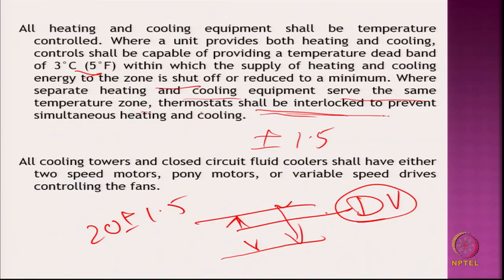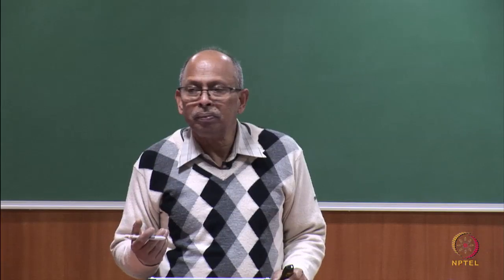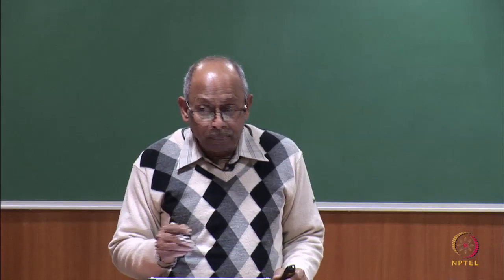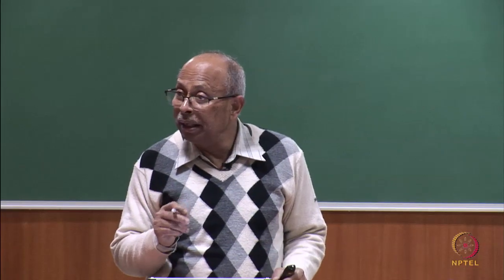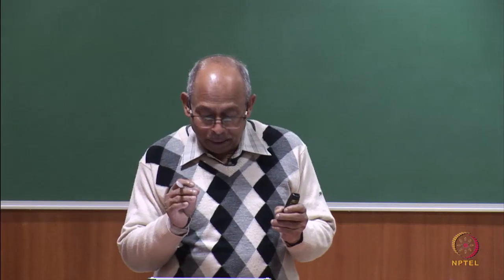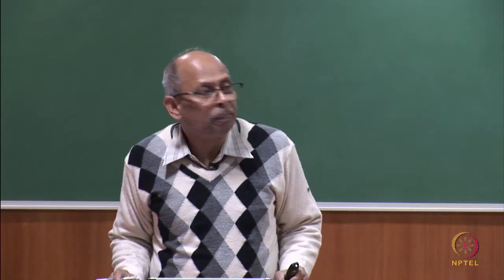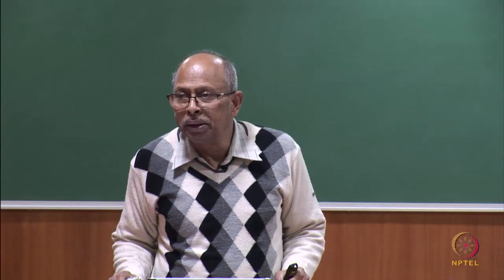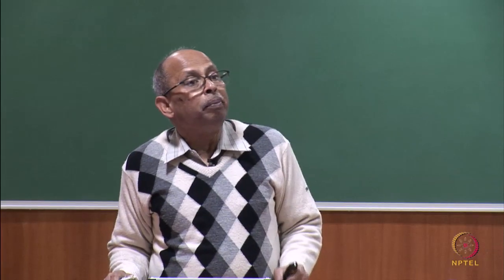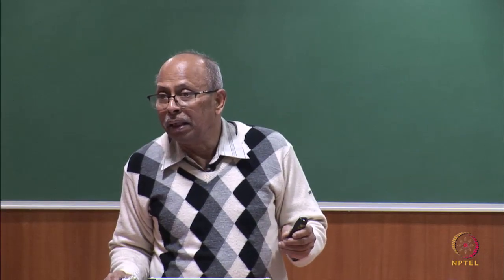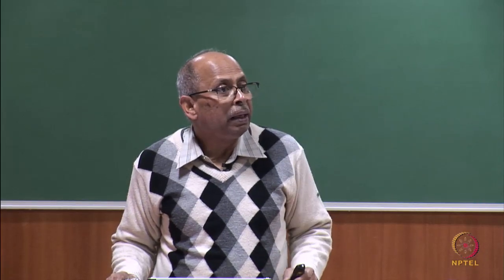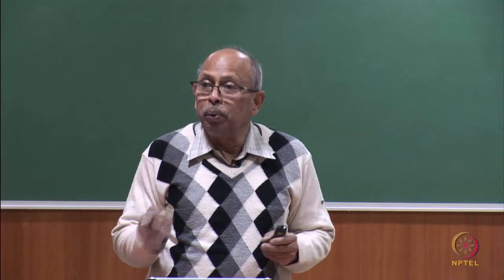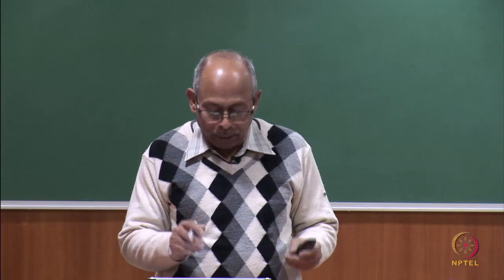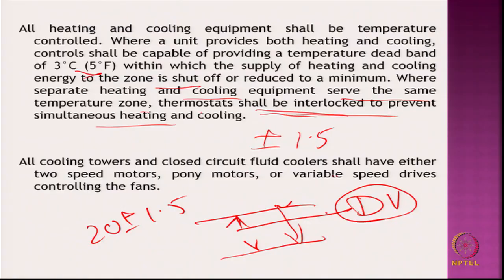And then, serving the same temperature zone, the thermostat shall be interlocked to prevent simultaneous heating and cooling. Simultaneous heating and cooling would not operate, because usually you require cooling in summer and heating in winter. Sometimes some places may need both, but not simultaneously. For example, a hospital is a 24-hour operation. In that case, maybe early in the morning you need heating and at the peak or end of the day you might need cooling, but you won't need both together, either heating or cooling. So that kind of control should be there.